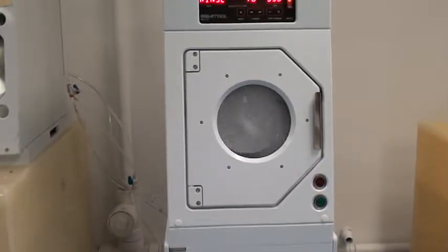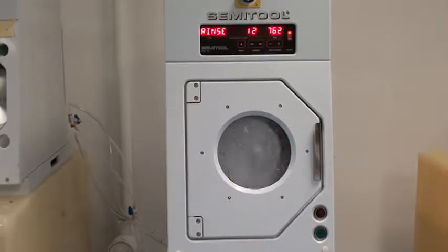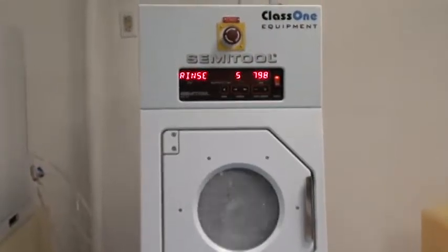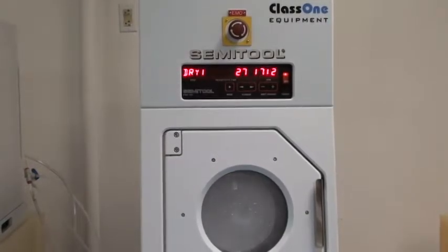The system's been fully refurbished and it's running quite well in the rinse step. Refurbishment is based on a complete disassembly and reassembly, during which the bowl is sent out for electropolishing. This system has a brand new custom rotor for the customer's 8-inch cassettes and wafers.